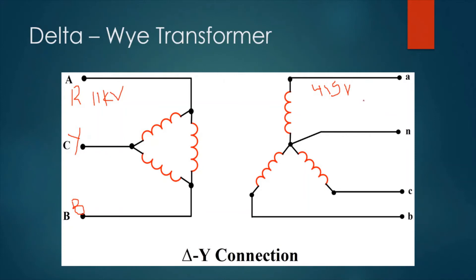The secondary side of this transformer is 415 volts, which will be connected to our devices and appliances. We notice that the secondary side has four terminals instead of three. These terminals are used for phases R, Y, and B, and the fourth terminal is for the neutral line, which is connected to the common point of the R, Y, and B phases. In other words, this transformer is actually converting a three-wire system to a four-wire system that can be utilized in our homes for different devices. If we measure the line-to-line voltage from R to Y phase, we will get 415 volts.